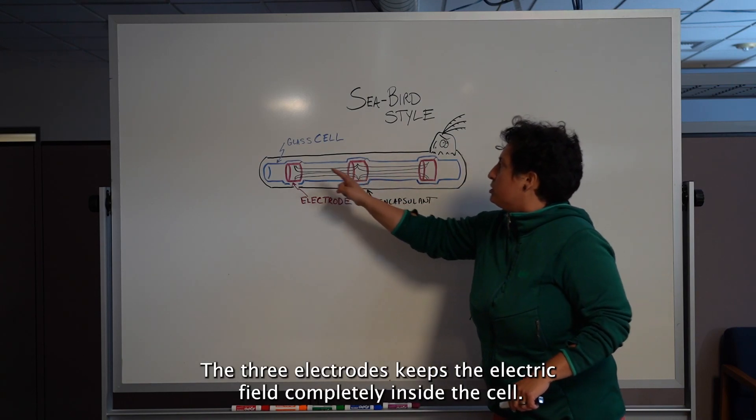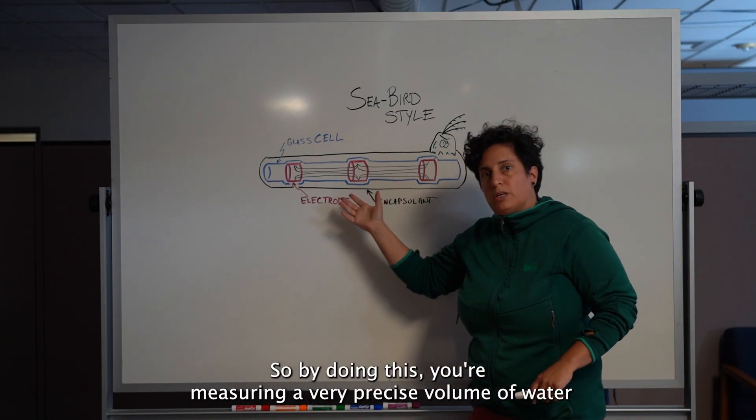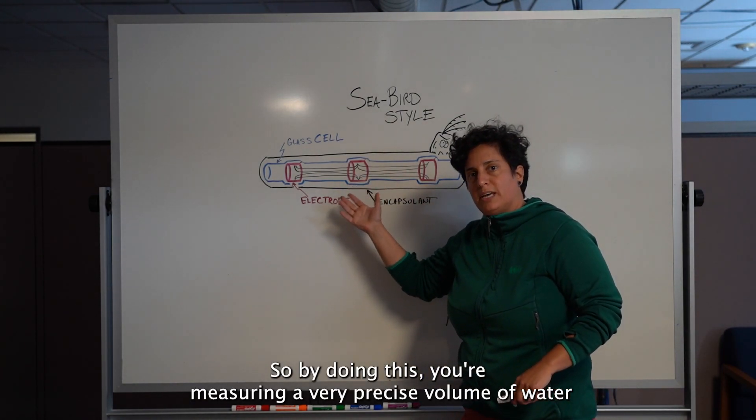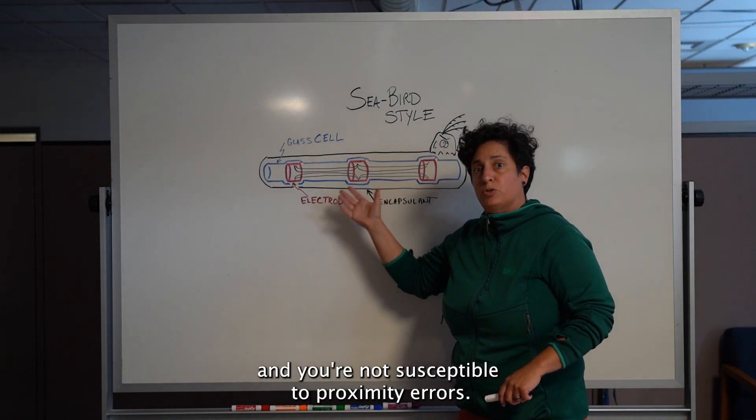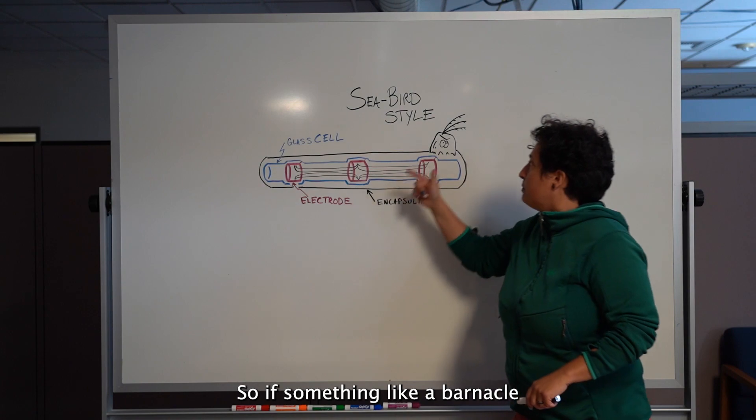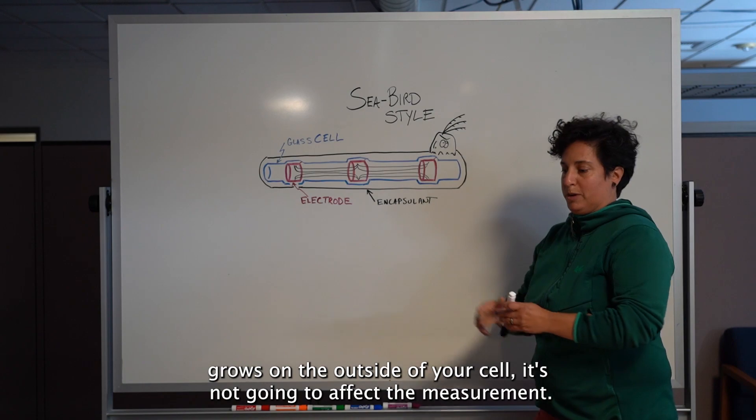The three electrodes keeps the electric field completely inside the cell. So by doing this, you're measuring a very precise volume of water, and you're not susceptible to proximity errors. So if something like a barnacle grows on the outside of your cell, it's not going to affect the measurement.